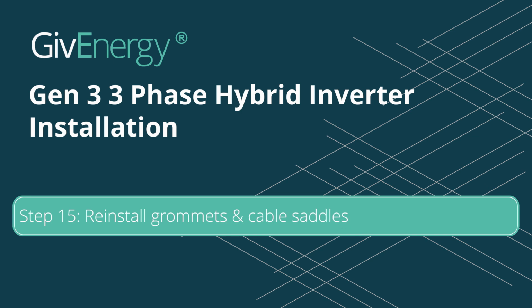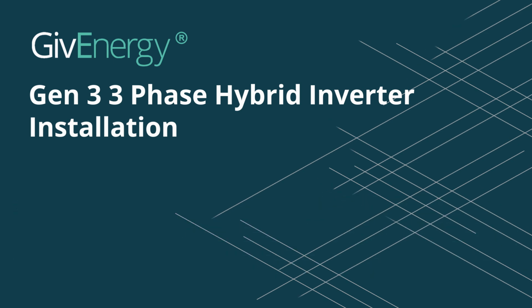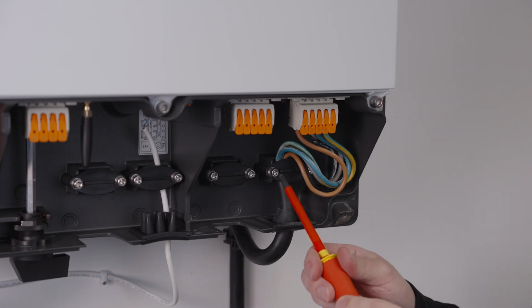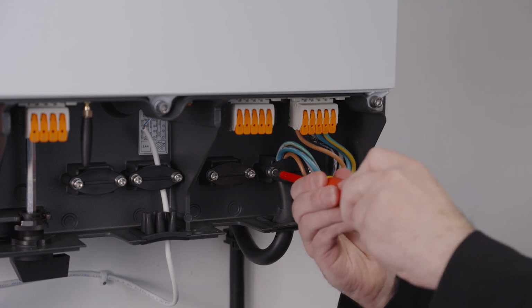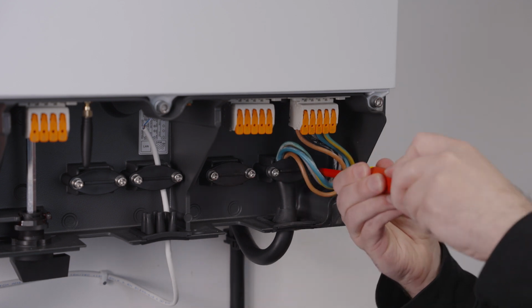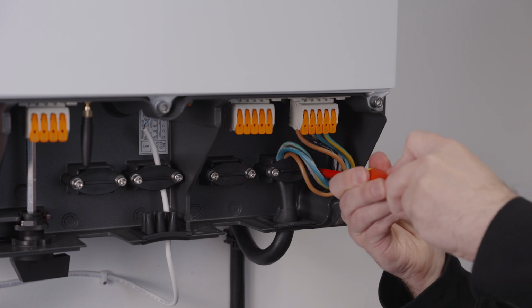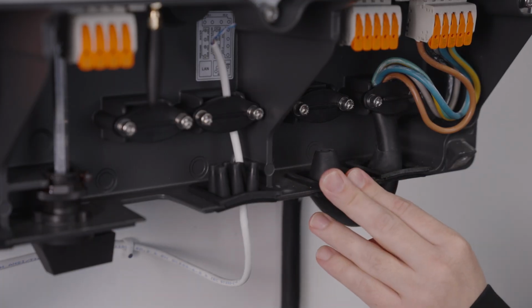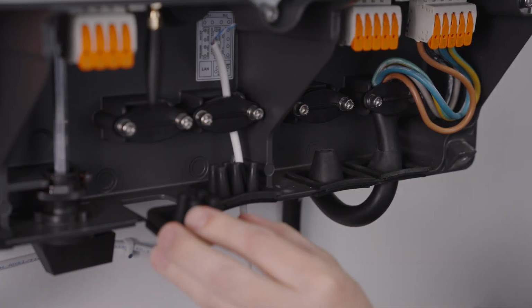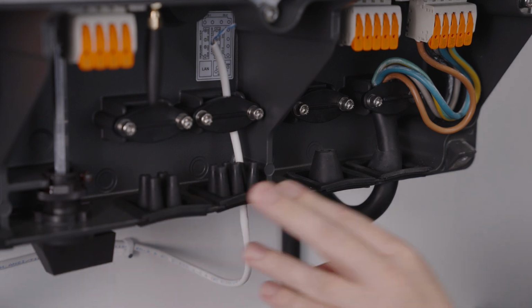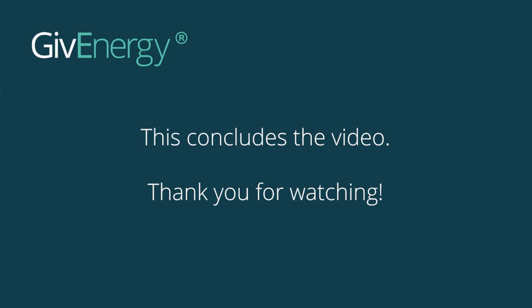Step 15. Reinstall grommets and cable saddles. When you are happy that all Wago or similar connectors and all cables inserted into the inverter are connected securely, reinstall the grommets and cable saddles using the Allen key. Ensure that there is adequate cable strain relief. This concludes the Hybrid Generation 3 3-phase inverter installation guide. Thank you for watching.